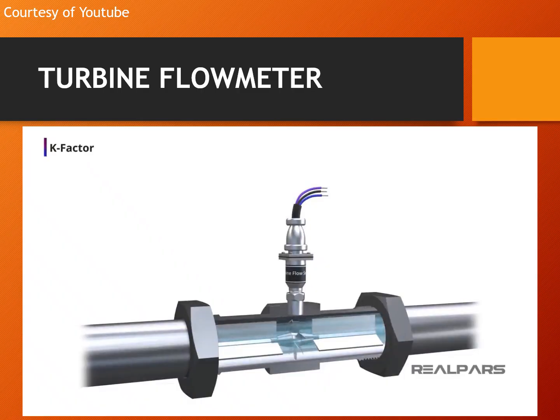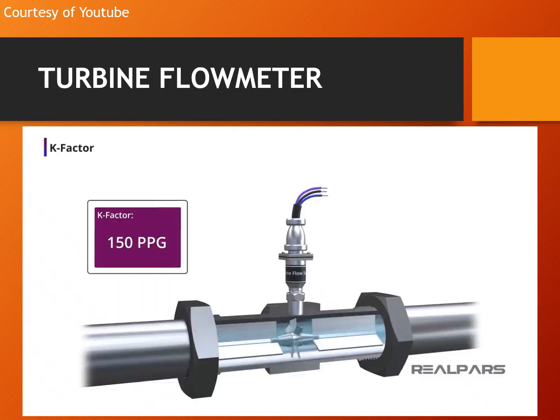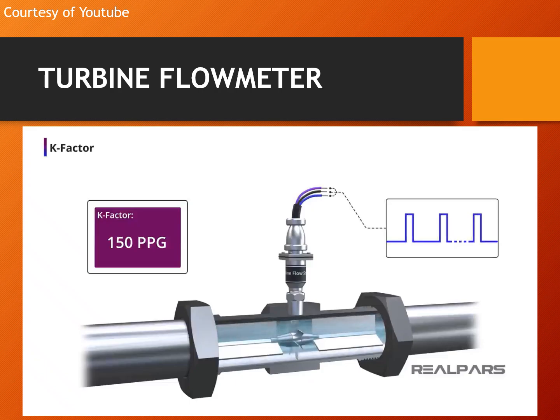Okay, so now we've reviewed fluid velocity and volumetric flow rate. Let's talk about how a turbine flow meter is used to measure volumetric flow rate. When you buy a turbine flow meter, it should arrive with a tag or a calibration certificate declaring its K factor. This K factor is unique to each and every turbine flow meter and is determined by the manufacturer. As we discussed earlier, the turbine flow meter will generate pulses, and the pulse rate depends upon the fluid velocity. The unique K factor declares the number of pulses that will be generated for every unit of product passing through it. K factor will be expressed in terms of the number of pulses produced, such as 150 pulses per gallon.